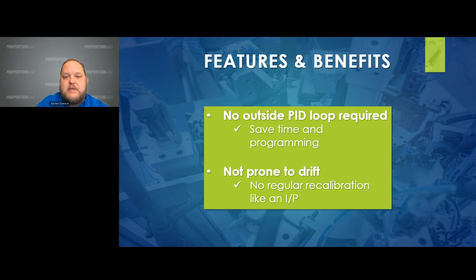You may have noticed that on our prior slides, you didn't see any reference to a PID loop. Ours are truly closed loop devices. No PID loop programming is required. The units come from the factory calibrated and ready to hook into your system without complicated programming. Another benefit over I2Ps is that our devices aren't prone to drift. If it looks like you're seeing drift, check the system for plumbing leaks, wiring, and electronic signal levels. Always verify the accuracy of your measuring equipment before recalibrating.